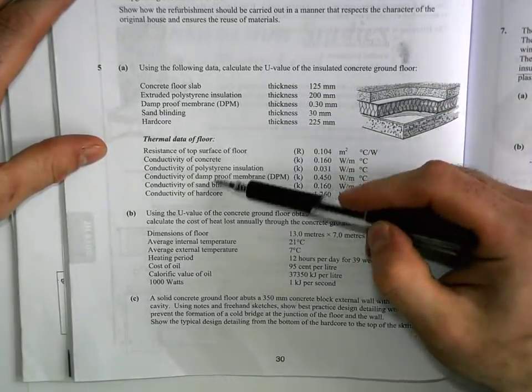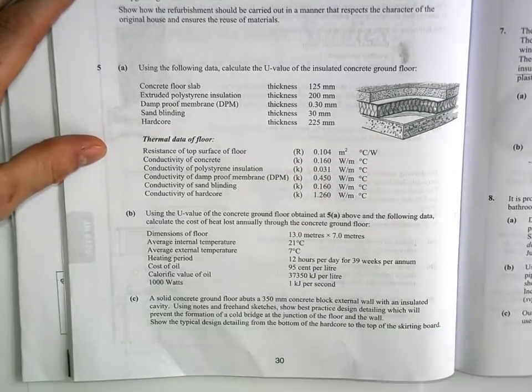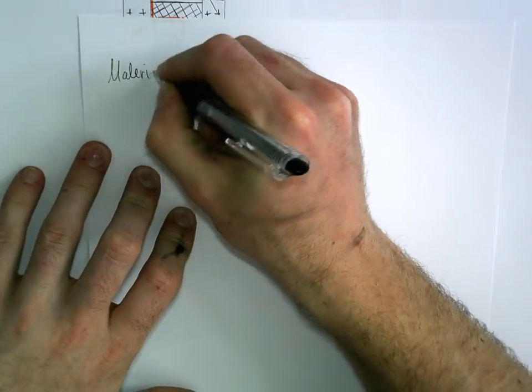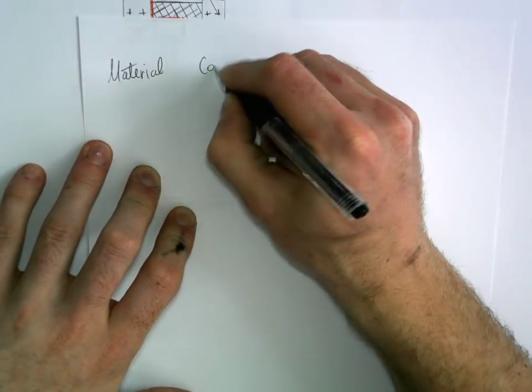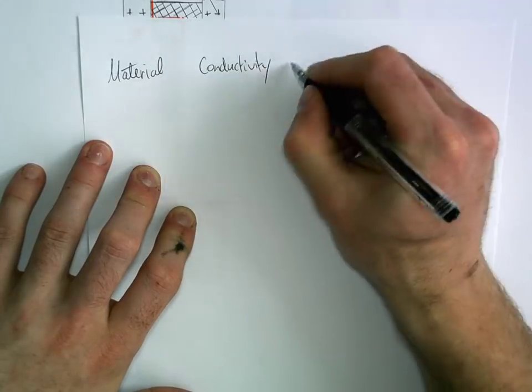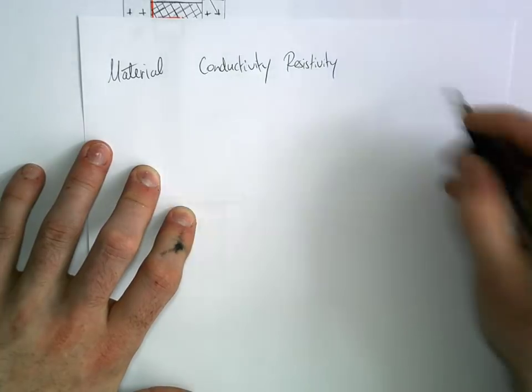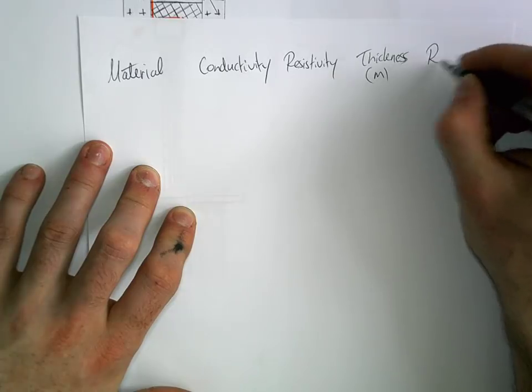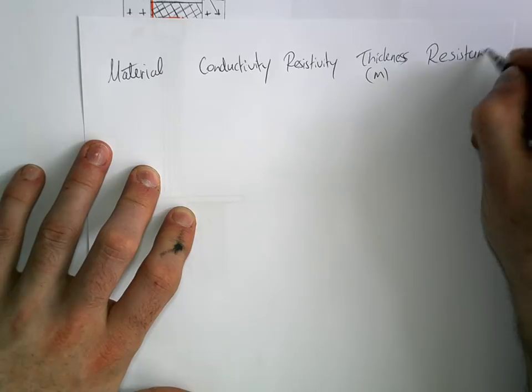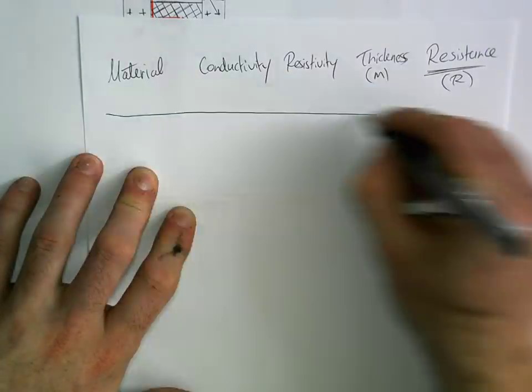If you look at Part A from 2014, you're looking at a concrete ground floor — you're given the thicknesses of all the different elements and the thermal data. For most of it you're given the k-value, which is conductivity, so we only use one formula. When answering Part A, always do it in a table format. The columns are: material, conductivity, resistivity, thickness — which must be in meters — and finally resistance, which is the important one, so box that off.